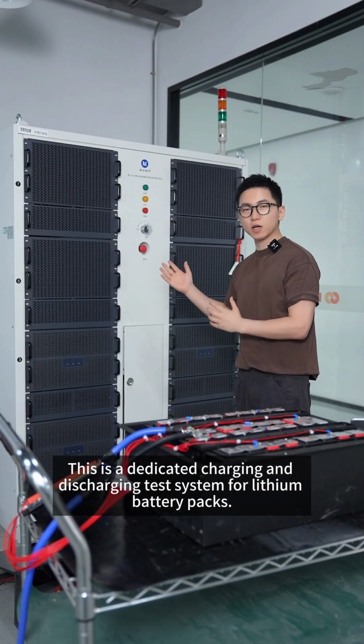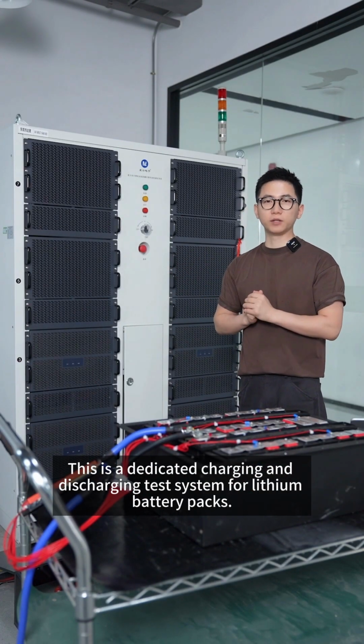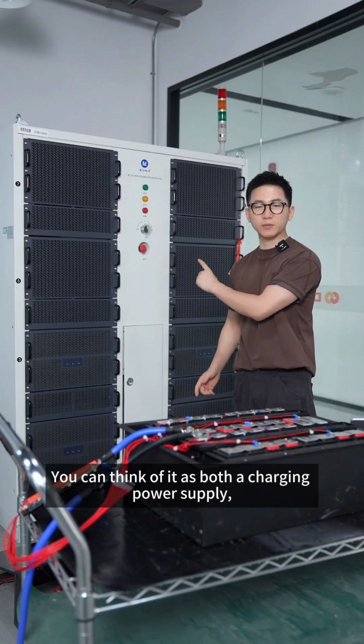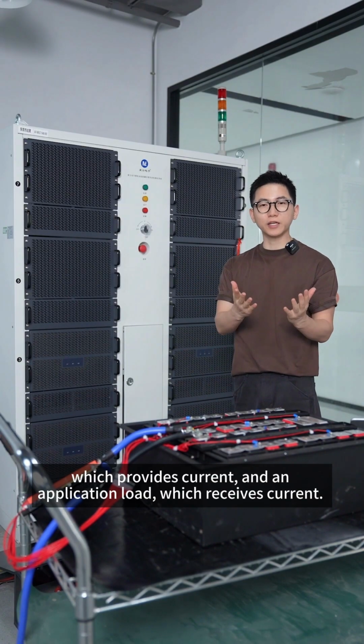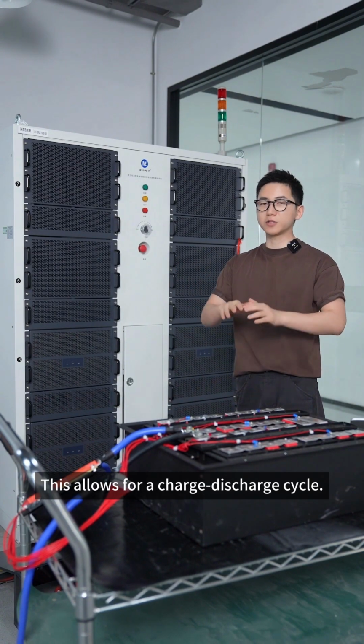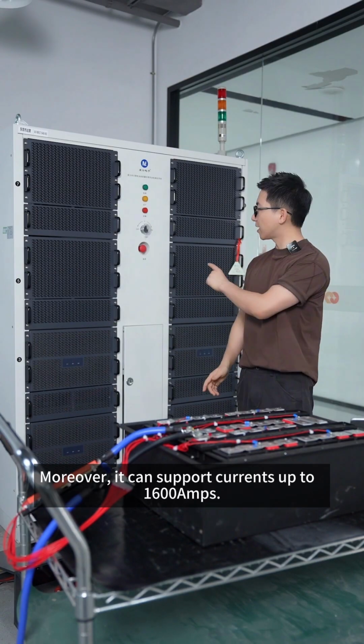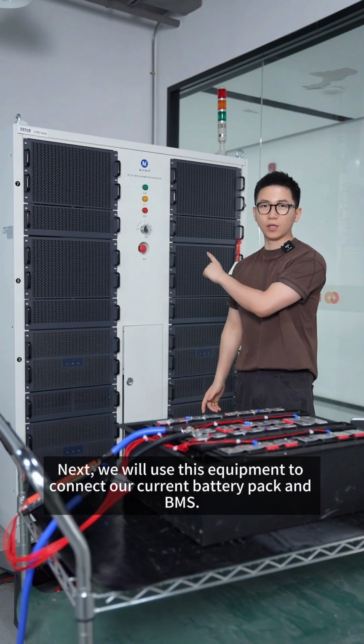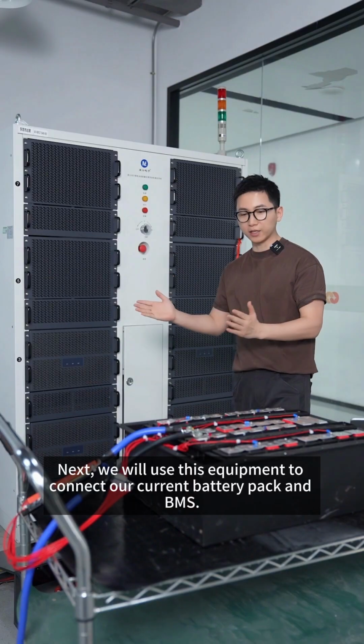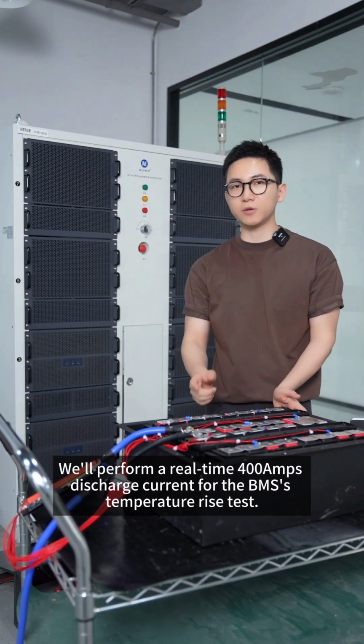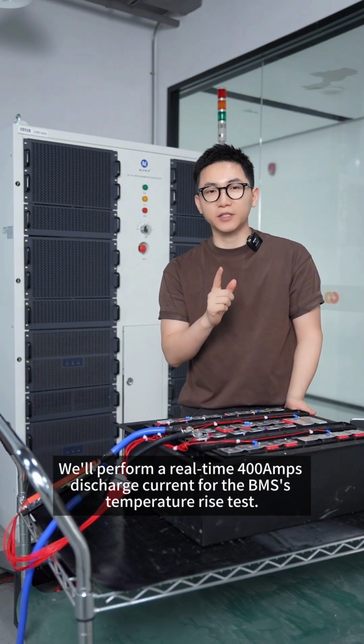This is a dedicated charging and discharging test system for lithium battery packs. You can think of it as both a charging power supply, which provides current, and an application load, which receives current. This allows for a charge-discharge cycle. Moreover, it can support currents up to 1600 amps. Next, we will use this equipment to connect our current battery pack and BMS. We'll perform a real-time 400 amps discharge current for the BMS's temperature rise test.